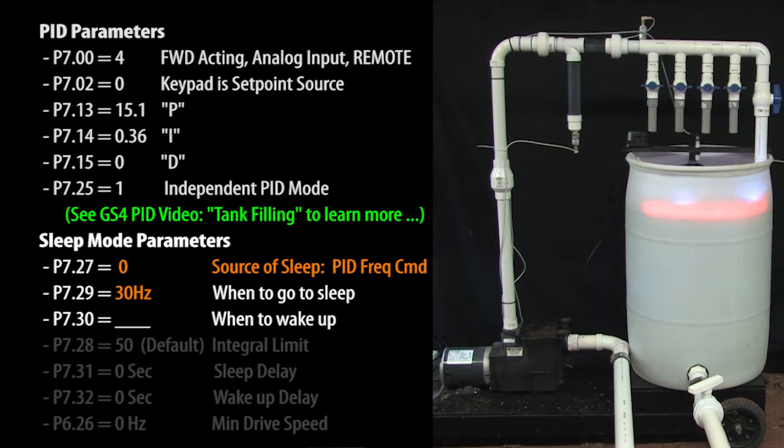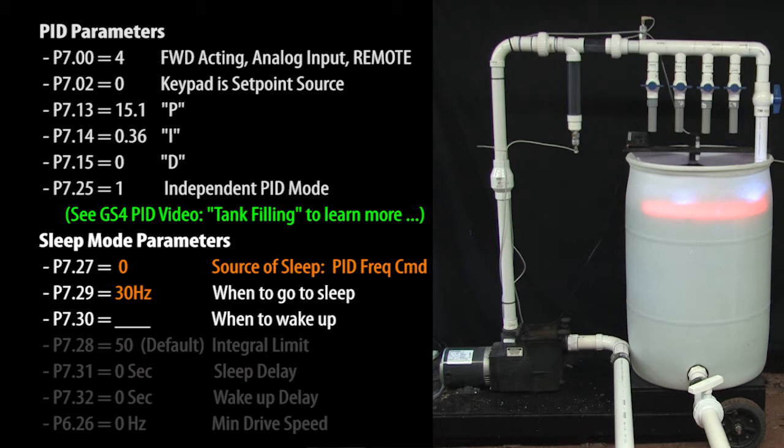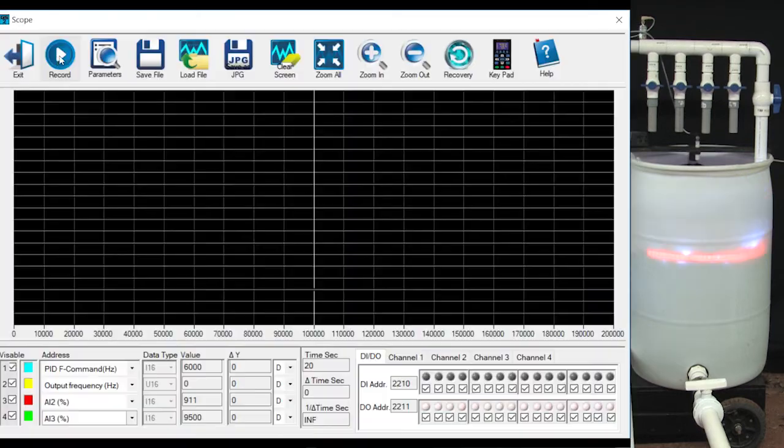As the water level falls, PID is going to automatically raise the command frequency to try and bring the water level back up. It can't because sleep mode turned the motor off. PID doesn't know that, so it will keep increasing the output frequency to try and get that water level to rise. Let's have sleep mode turn the motor back on when PID pushes the command frequency past 50 Hz. Well, that's all there is to enabling sleep mode 2. Let's try it.